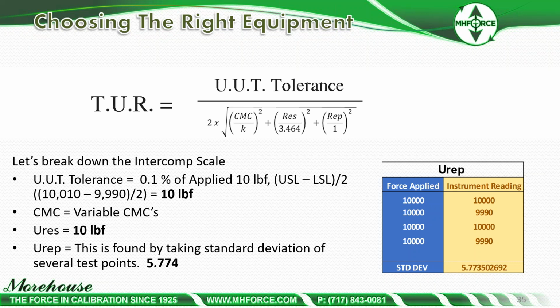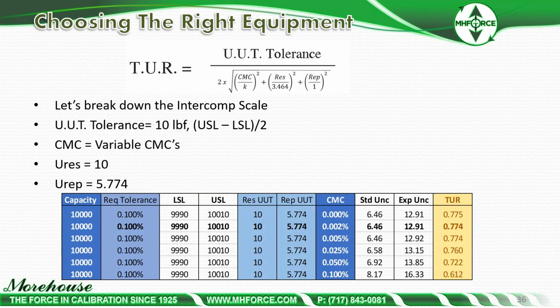We start looking at it. Here I'm showing a standard deviation. Here's how we get repeatability. We make multiple measurements and we take the repeatability of those measurements. So right here, I take 4 measurements and my standard deviation is 5.77 pounds. So that's what I'm going to look at. And my resolution's 10 pounds. That's not going to change. That's what the device, you're going to have to buy or have the manufacturer, which they probably could cut the resolution down to 5 pounds or something that would make this a lot better.